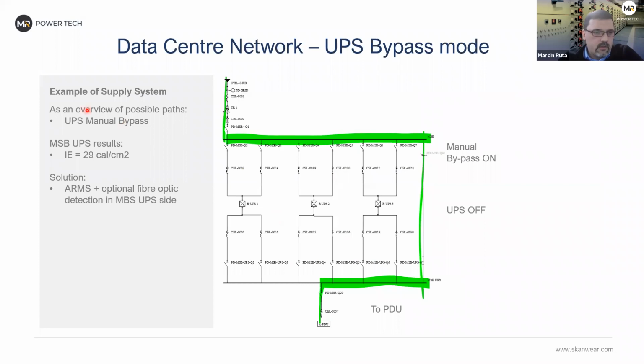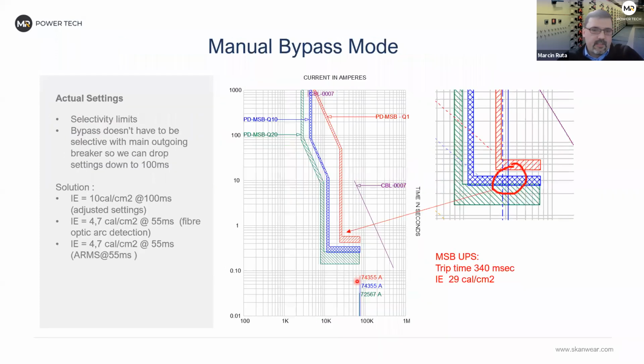If we go further, we have manual bypass, and manual bypass was the highest energy. And in this case, I was looking at the ARMS and fiber optic. Physically, it looks like this. So with ARMS, we can go down to 4.7, and very similar will be for fiber optic, 4.7 calories, because they should have similar time to trip. And it was possible to set it like this. So there's a big difference from 29.